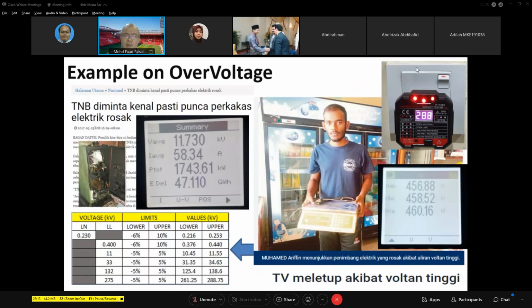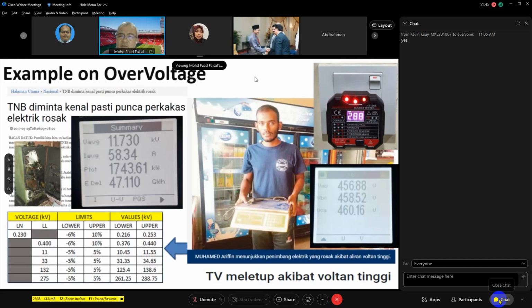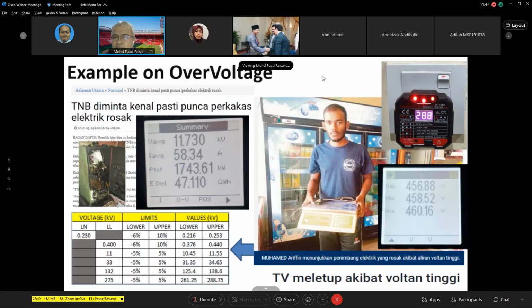Again, we're talking about power quality, but as mentioned, there are regulations required by the regulator for the utility. So if you are experiencing, you can see on my right hand side, on the top of the slide, a socket tester showing voltage of 288. This is over voltage. Myself as an engineer, a TNB engineer, I have a lot of gadgets. For example, the socket tester you can see on the slide. I have around 7 of these.